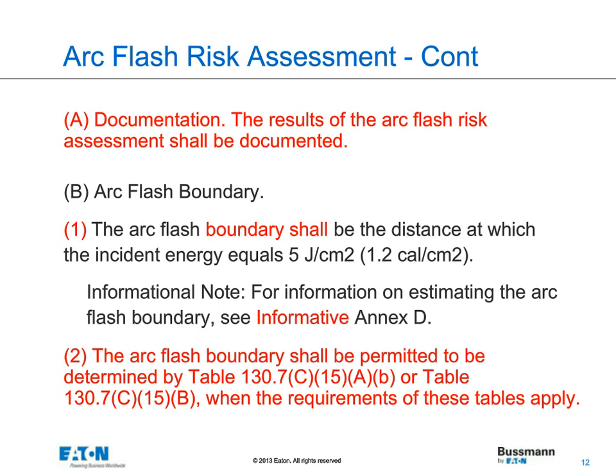Moving on to the arc flash hazard risk assessment. So we have the basic requirements and some information on those we just covered. Now we're moving on to a new part here, and in Part A, they again stress the importance of documentation. So per the requirements of 70E, as well as the requirements for OSHA, we have to document that we've done an arc flash risk assessment. Part B talks about the arc flash boundary. There used to be a note there that it was 50 volts or less, but now that has been deleted from that text.